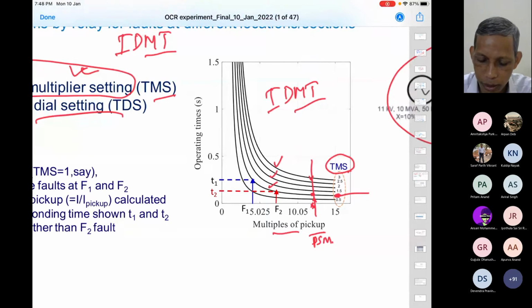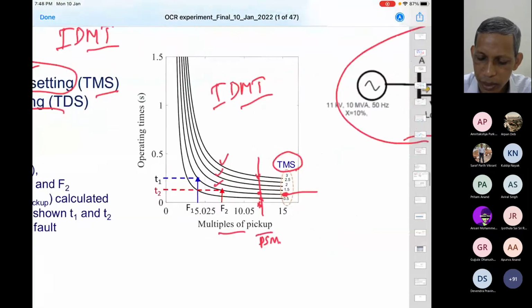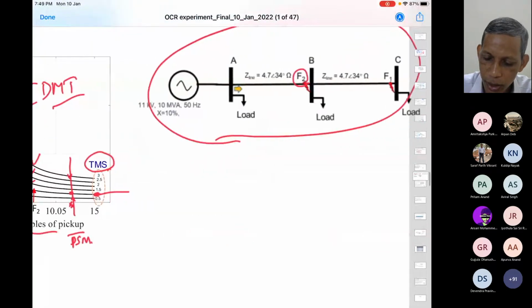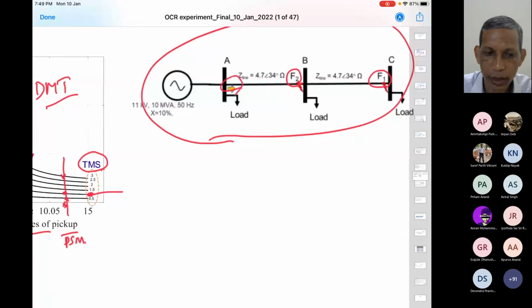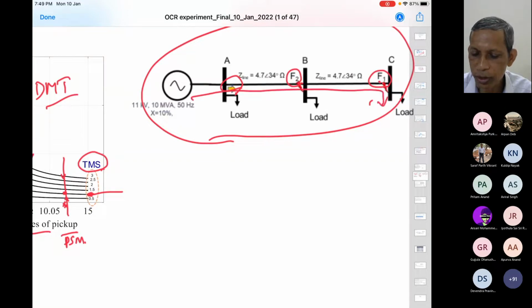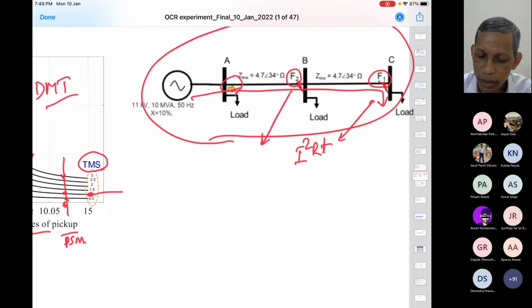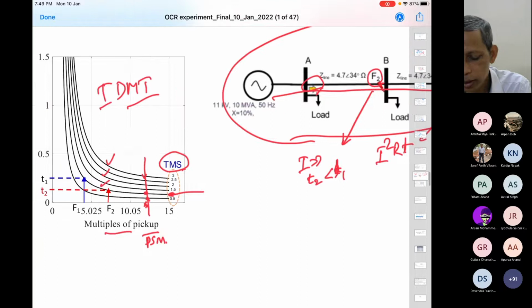Now, in this perspective, let us say in this system there is an F2 position and there is an F1 position. If we are looking at this relay, F1 is further and F2 is closer. So for an F1 fault, because current will be smaller, from this side current flows, the decision time should be more. Again, I square RT governing. And for F2, fault level is higher, so the time should be smaller. T2 should be smaller than T1. T1 for F1, T2 for F2. Agree?